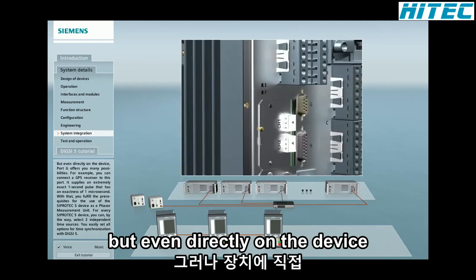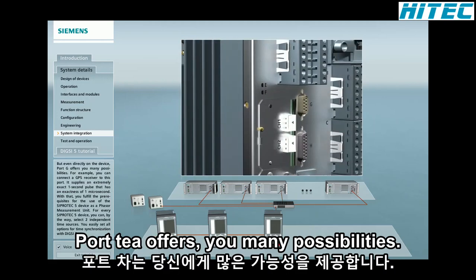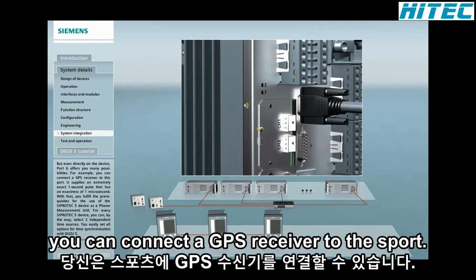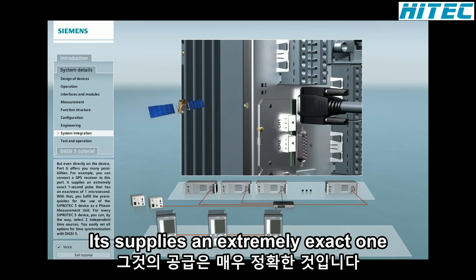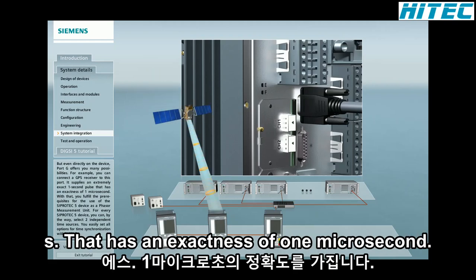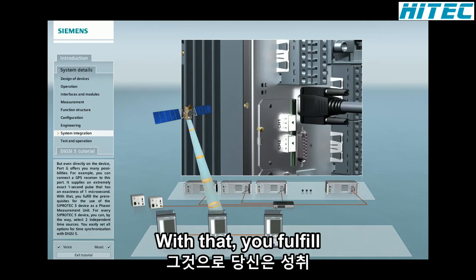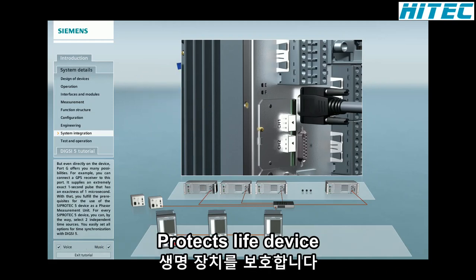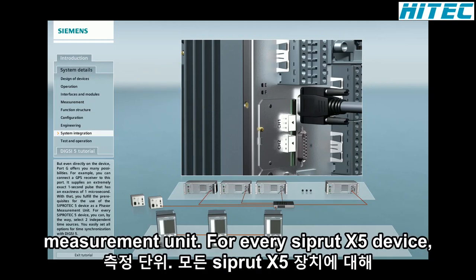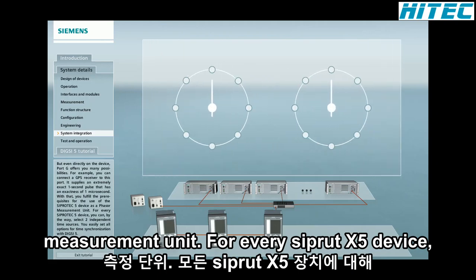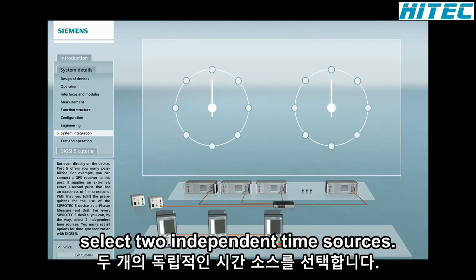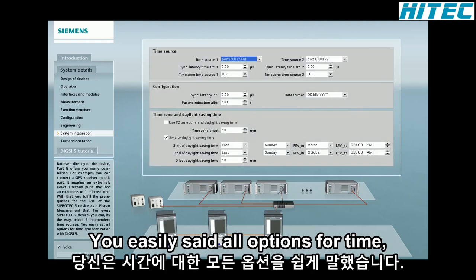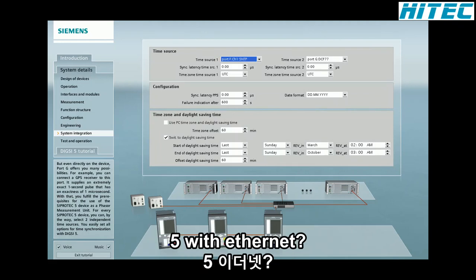But even directly on the device, port G offers you many possibilities. For example, you can connect a GPS receiver to this port. It supplies an extremely exact 1-second pulse that has an exactness of 1 microsecond. With that, you fulfill the prerequisites for the use of the SIPROTEC 5 device as a phasor measurement unit. For every SIPROTEC 5 device, you can, by the way, select 2 independent time sources. You easily set all options for time synchronization with DIGSI 5.